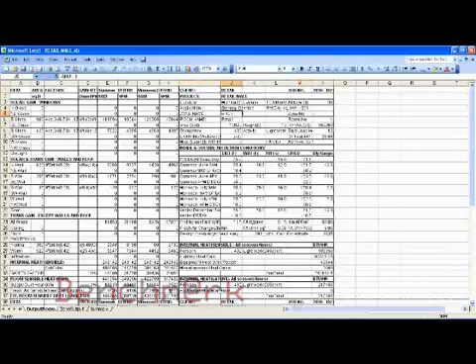This is the output of the software used for cooling calculation. Parts 1 and 2 you have already seen. In this Part 3 we are going to see the software output for cooling load calculation. All data is presented in BTU per hour. The formula used is Q = A × U × ΔT, where A is area in square feet, U is the overall heat transfer coefficient, and ΔT is the temperature difference. Q is the total heat in BTU per hour.